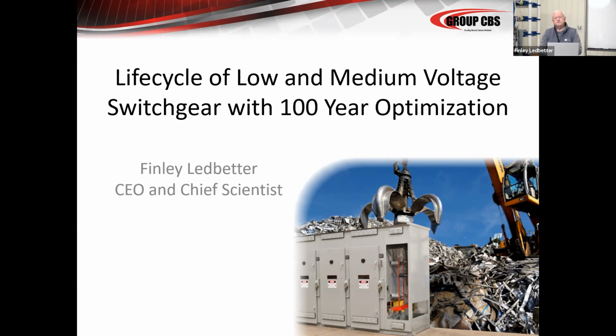First, obviously, it was SF6 or gas breakers. That did not work because of a lot of issues. They're fairly complex. You have the gas issue, you have pressure seals, pressure transmitters that create leaks, and then you have the environmental concerns. So a lot of things stacked up against gas. Actually, gas was a good idea and an excellent way to go about this problem. But vacuum through all this has become the standard.